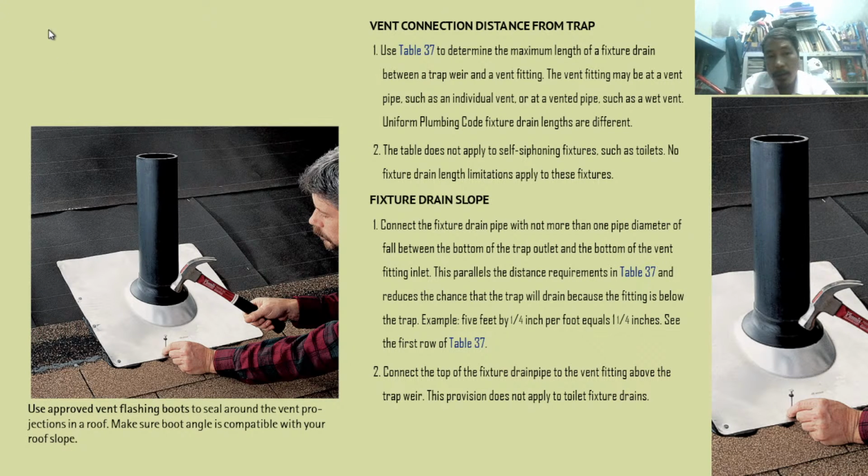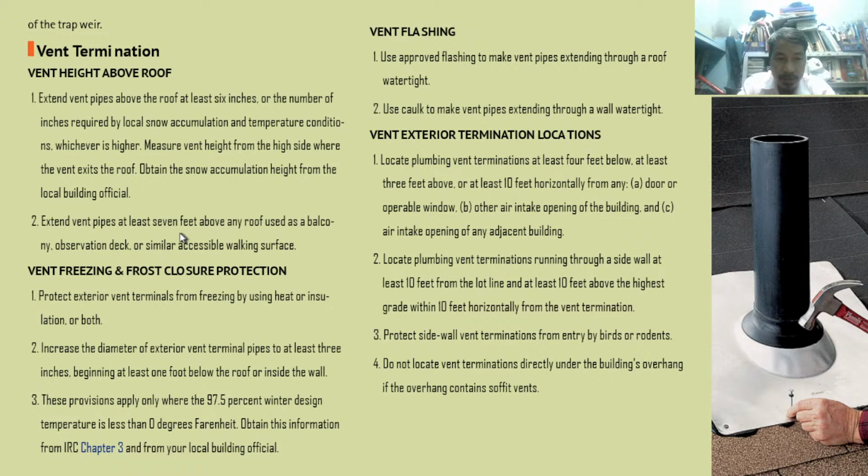Okay. But if this roof is being used as occupancy, for example, for balcony use, therefore there are people that may be staying there for some longer period of time, hours and hours of stay of occupants. So we need this pipe to be as high as 7 feet.